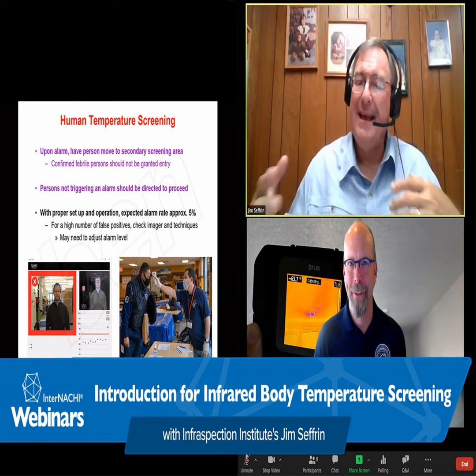With respect to thermal imaging systems, when you are using them to ascertain a person's body temperature, regardless of what they were built for, they are now being used for medical application. And prior to April this year, the US FDA required that you had to have a 510K clearance for this equipment. Now that 510K clearance is not something that is widely applied or available on industrial imaging systems.